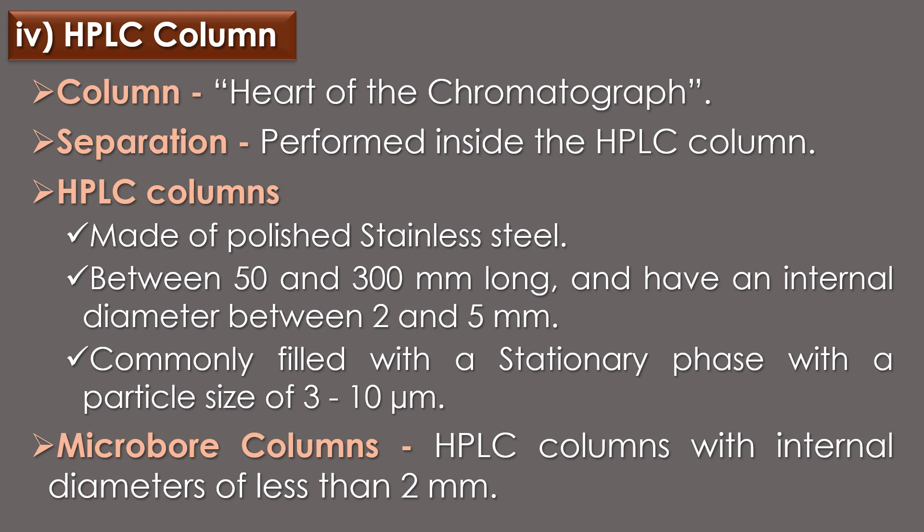The HPLC column is considered the heart of the chromatograph. The separation is performed inside the HPLC column. HPLC columns are usually made of polished stainless steel because stainless steel is tolerant towards a large variety of solvents. HPLC columns are between 50 and 300 mm long and have an internal diameter between 2 and 5 mm. HPLC columns are commonly filled with a stationary phase with a particle size of 3 to 10 micrometers. Columns with internal diameters of less than 2 mm are often called microbore columns.